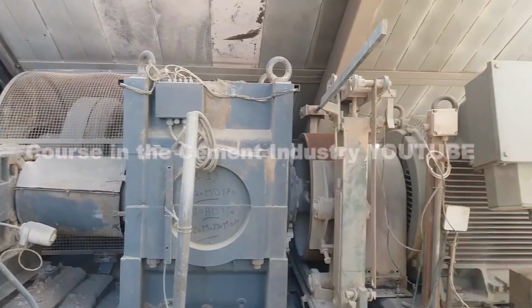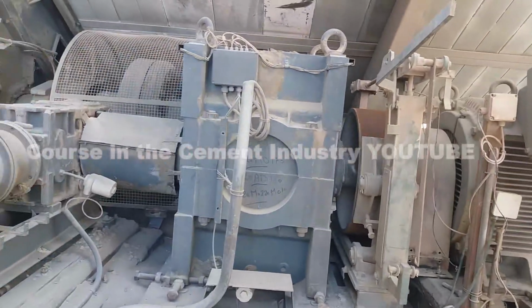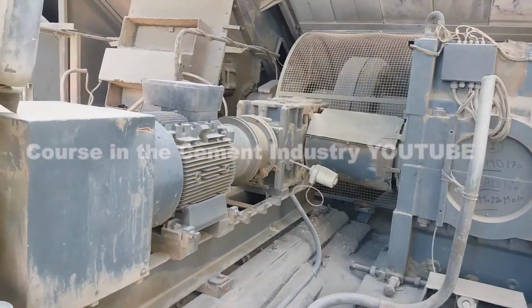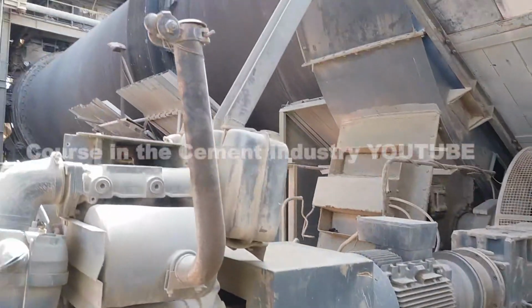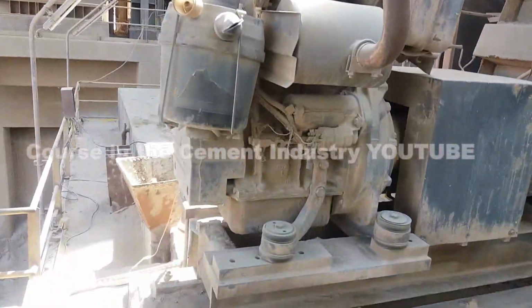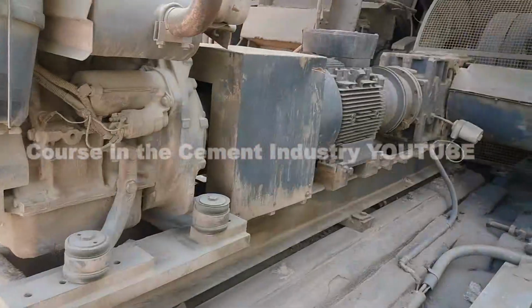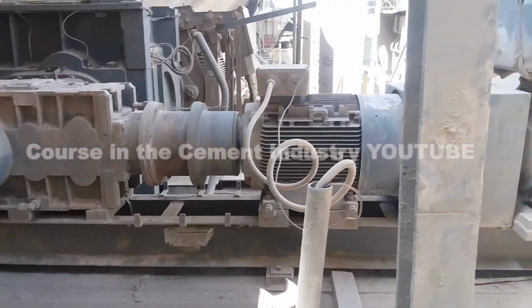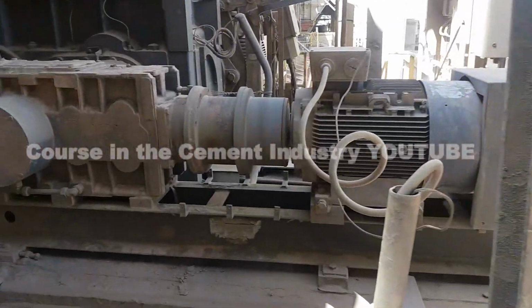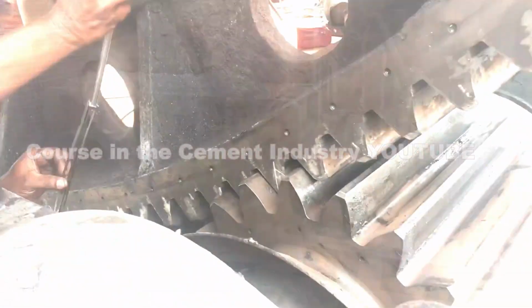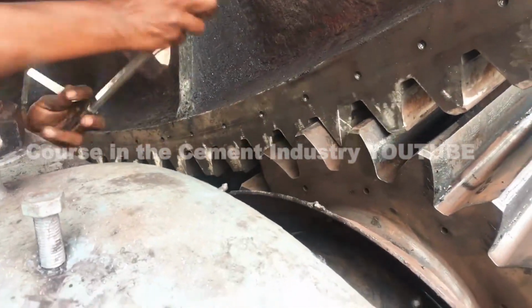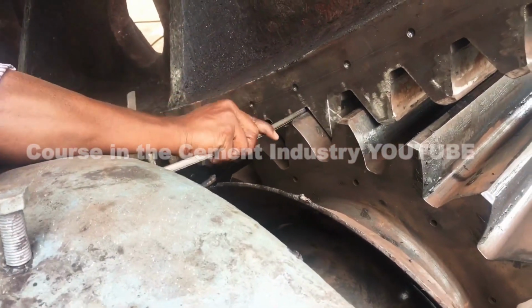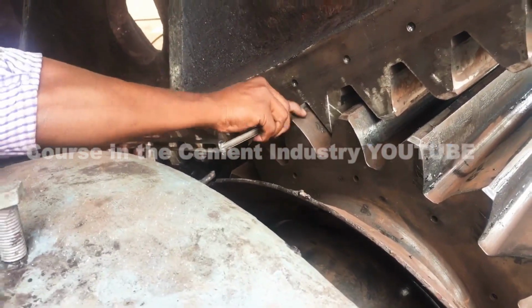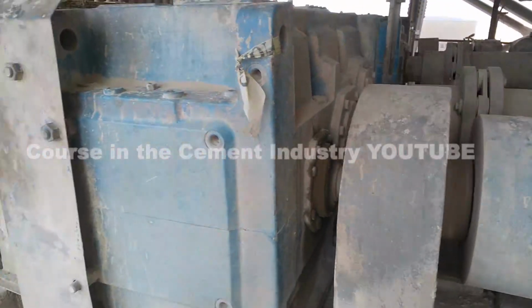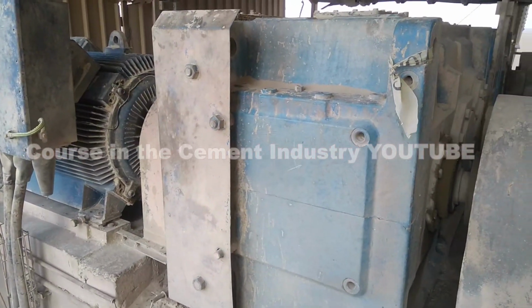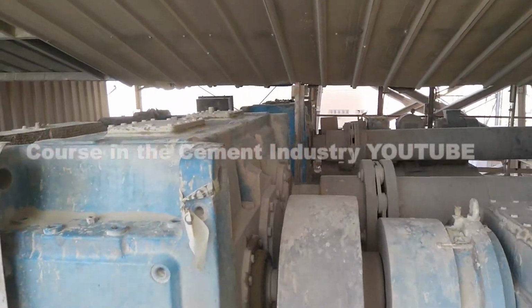B. Maintenance and monitoring parameters. To prevent catastrophic failure, the following are monitored 24 hours a day, 7 days a week. Parameter, why it matters. Gear vibration: high vibration indicates misalignment or worn teeth. Lubrication temperature: overheating suggests gear friction or gearbox internal failure. Pinion/gear mesh: checked using lead wire tests to ensure even contact across the tooth width. Motor amperage: a sudden spike in amperage indicates a mechanical obstruction or coating fall inside the rotary kiln.